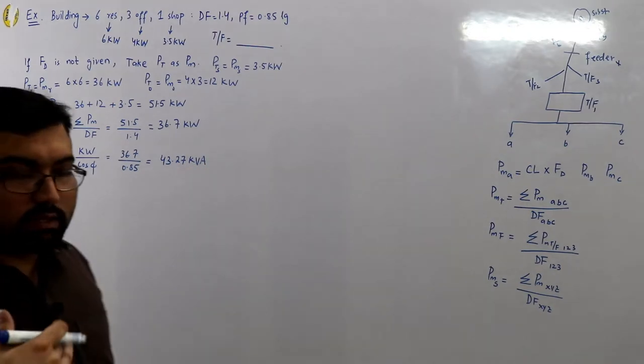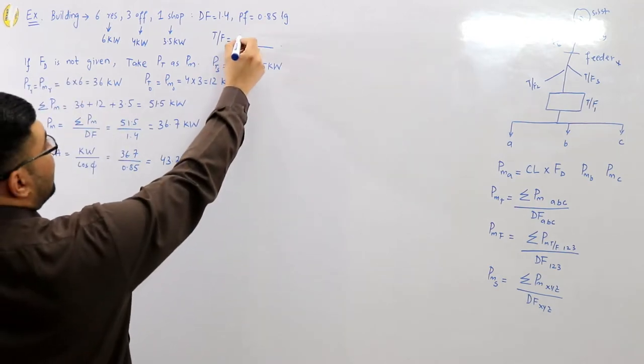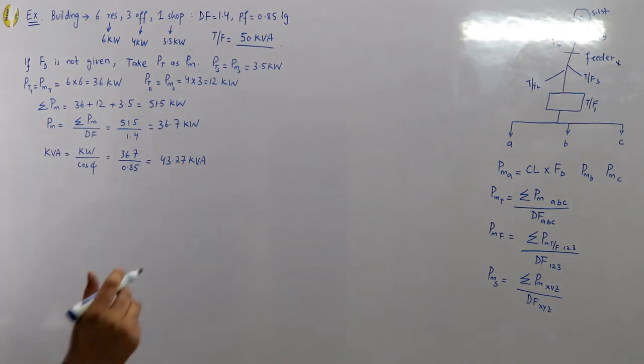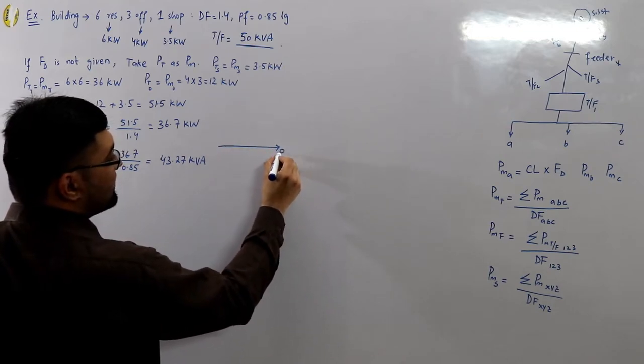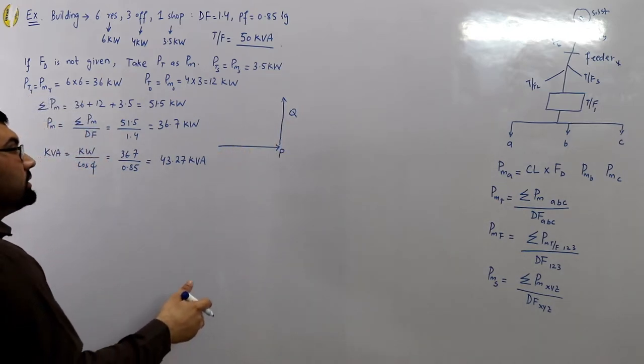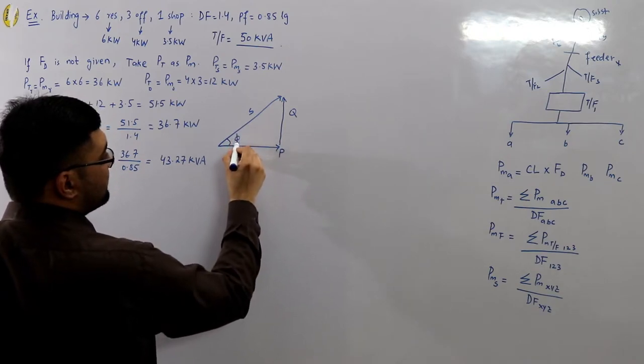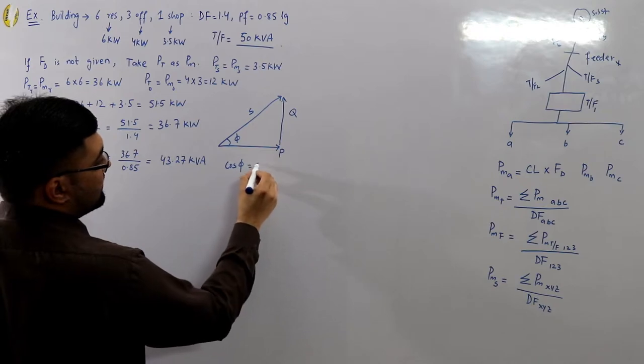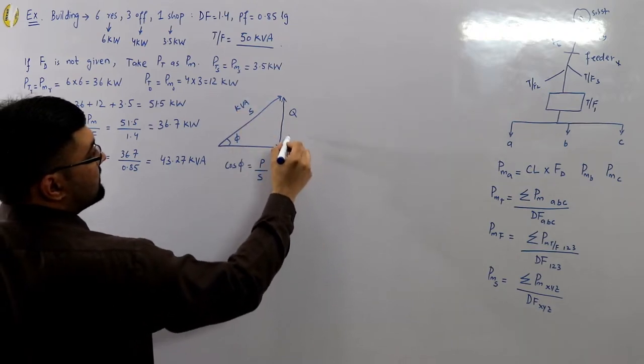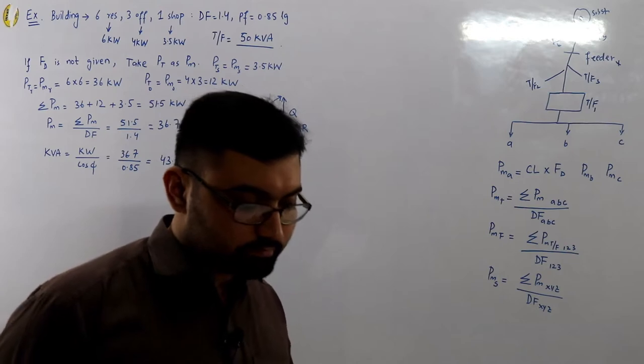The available transformer should be a little higher than 43.2 kVA, so I would suggest a 50 kVA transformer for this building. Regarding power factor: real power P is on the x-axis, reactive power Q is upward or downward depending on inductive load, and apparent power S is the hypotenuse. cos φ = P / S, where S is in kVA, P is in kilowatts, and Q is in kVAr.